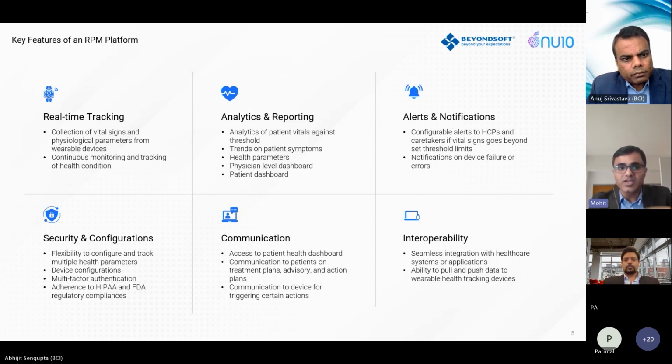So it's a two-way communication. For an active device, a physician could very well feed what the dosage is, for example, and the class 2 or class 3 medical device could actually be using that as an input variable while managing patient care.